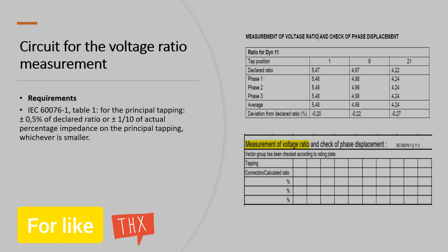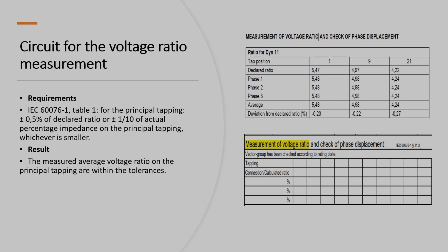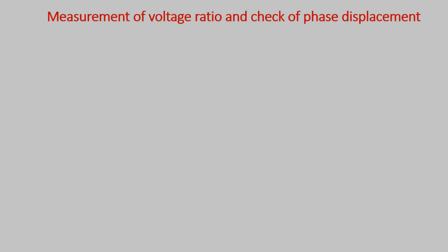This requirement is under IEC 60076-1: the principal tapping tolerance is plus and minus 0.5 percent of the declared ratio. This is the principal tapping value, which is very small. The result shows that the measured average voltage ratio and the principal tapping are within that tolerance.